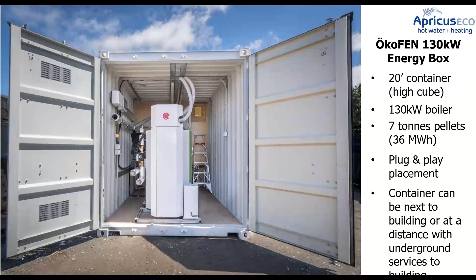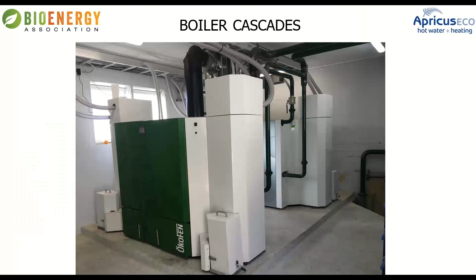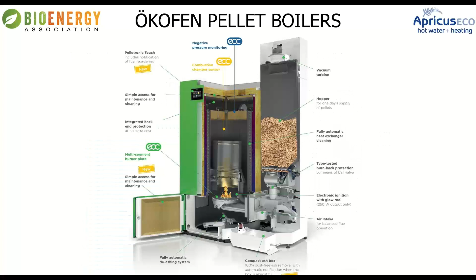When it starts, here's the fan, 1.3 kilowatts, but only for 5 minutes once a day. And then the igniter, that's 250 watts. But again, that's for a few minutes when it first starts. And if it's got multiple starts in a day, it won't even use that. It will just use air and residual heat. So when it's ticking over, it's using about 300 to 400 watts. So half a kilowatt here, and we've got 130 kilowatts here. So if you want to work out the COP, we've got 130 divided by 0.5, so we've got a COP of 260.